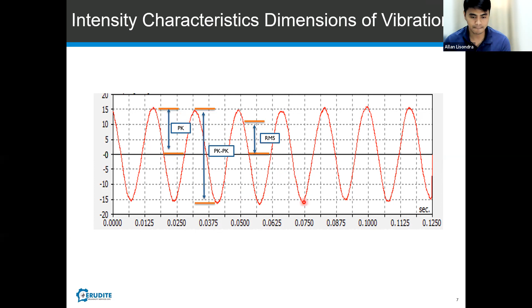So we have the time waveform and frequency. For example, let's say we have equipment with a motor and gearbox. For this, we have a fast Fourier transform. On the left side, you see the complex time waveform, which is composed of many frequencies. Let's say this is the frequency for your operating speed, and this one is for the harmonics of your operating speed. Another is for the bearing, and another is for the gearbox.